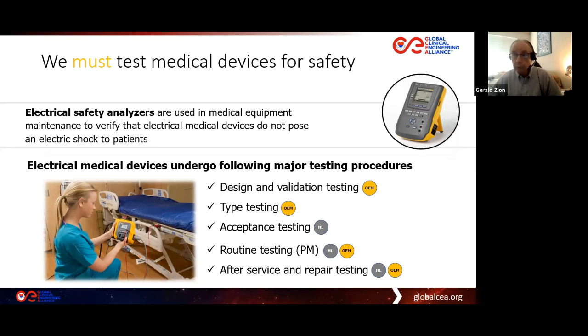And we need to also repeat this testing anytime we have done a repair, opened up the medical device at all, broken the isolation barriers. We need to repeat the electrical safety testing and measurements and document them to make sure that we have returned this medical device to safe and effective use.